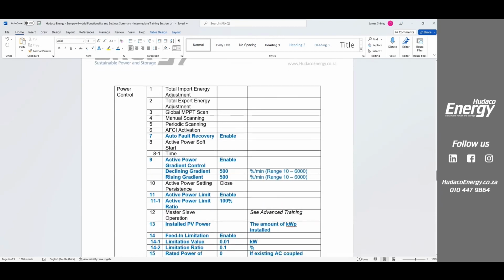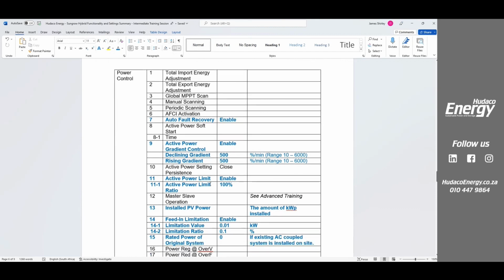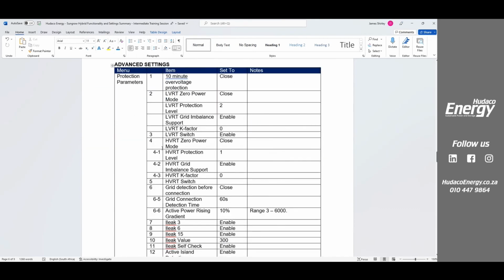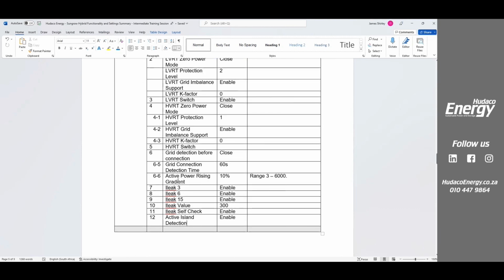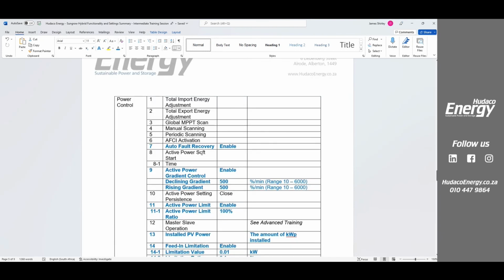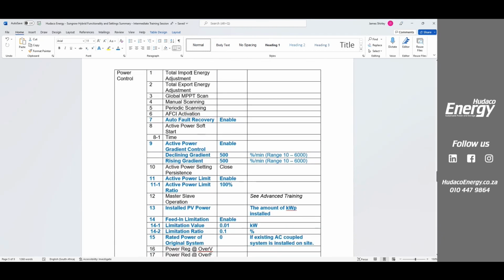Okay. The next one is power control. So you see in the protection, most of the stuff we've already got set. You may want to change active power rising gradient. So this is how fast do our panels respond. Everything else you can just leave. Once we get to power control, there's some things which you want to check. So, I mean, we can look here, the different ways of MPPT scanning, arc fault detection. What is important is auto fault recovery. Please make sure that that's enabled.